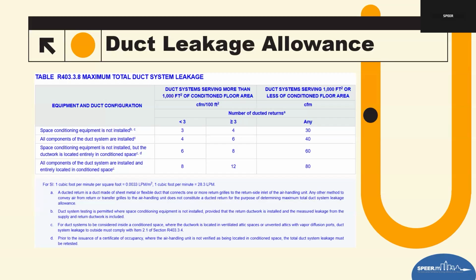which is simple but does not reflect real world HVAC designs. This is where going through the code and having more stakeholders involved in getting the code written actually had smart things to say to get things changed in the book that helps everybody, in my opinion. So there are 2 columns here, one for homes that are over 1,000 square feet, which is the one in the middle, and then for homes that are less than 1,000 square feet on the right. For homes that are 1,000 square feet or more, the leakage allowance is expressed, as always, in CFM per 100 square feet. It basically varies based on the number of returns.